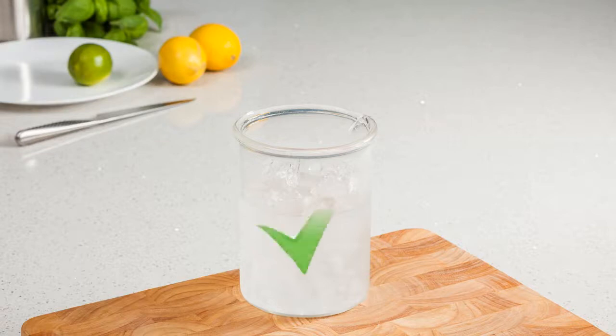Your ice point is now ready for use and can be topped up as necessary, depending on how long it's needed. Simply add more ice, but remember to drain any excess water.